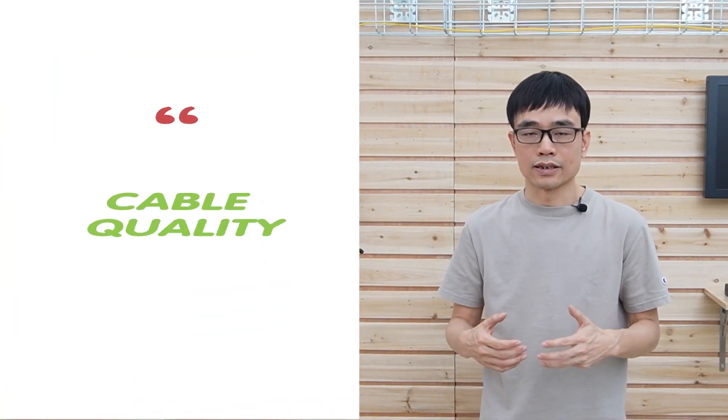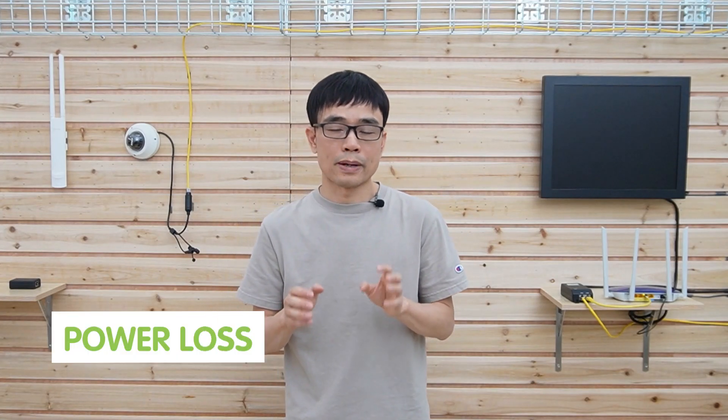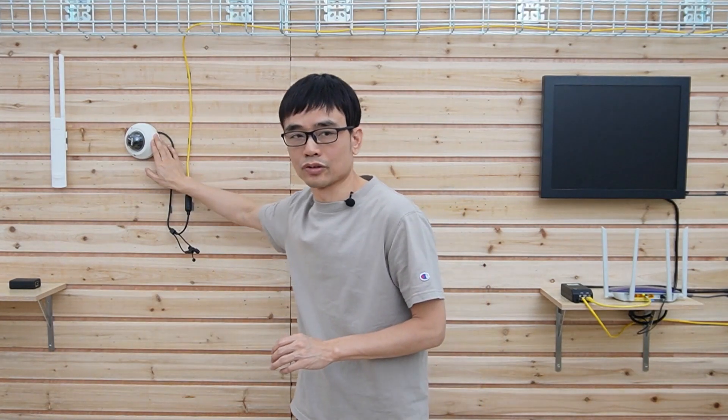And the next thing is about the cable. The cable is quite important because the power needs to go through this cable, and there's always power loss. If you just use low-quality cable, such as the CCA type, it will generate serious power loss. You may not have enough power at the edge.